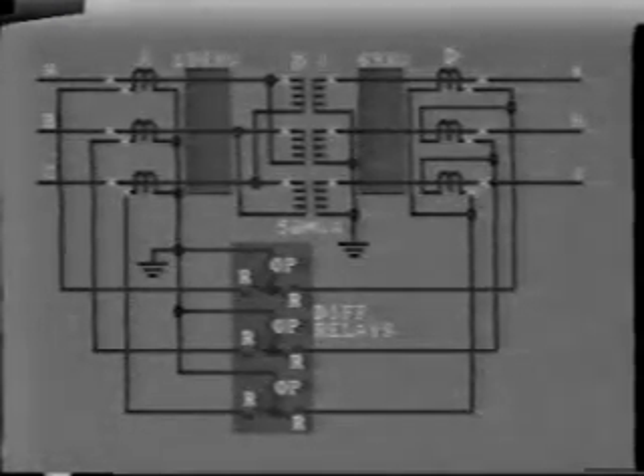Checking the CT connections for transformer differential protection is more complicated. Remember, where the transformer is connected in delta Y, the CT secondaries will be connected in Y delta. This factor must be allowed for when measuring secondary currents during the primary injection test. Where large, high-voltage transformers are concerned, it is likely that the test set will not have sufficient capacity to pass adequate test current through the transformer impedance.